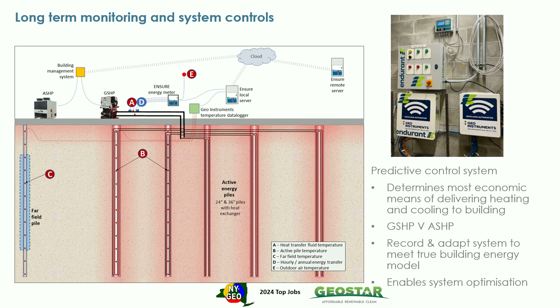That enables us to recondition the building to the way we want to operate it. What we've created here is a thermal battery. The target is, in summertime, we want the ground under that building to be around 40 degrees Fahrenheit, and in wintertime, around 90 degrees Fahrenheit, because as you run into those seasons, we can deliver really energy efficient heating and cooling.